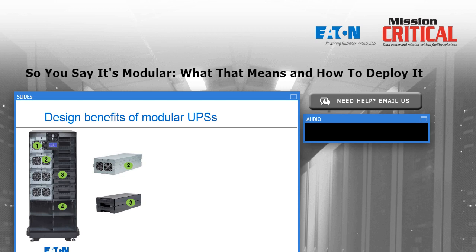And the user is not restricted to one battery module per power module. They can start out with a lot of power modules and a very few battery modules if they don't need much backup time. Or if their requirement is for longer battery backup time, they can put in 1 or 2 power modules and fill the rest of that right-hand side of the cabinet with battery modules and have a lot more backup time, all using the same frame of the UPS system.